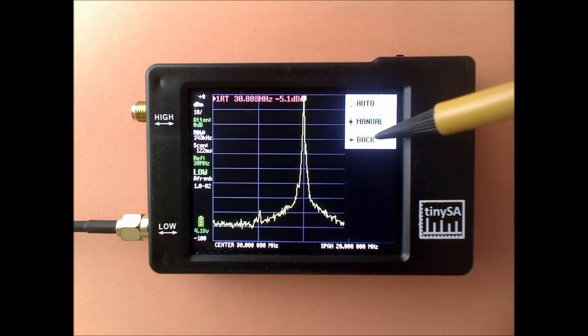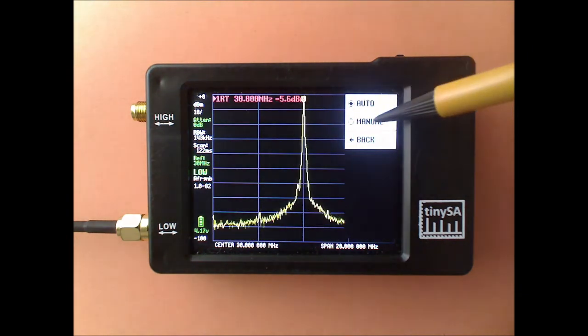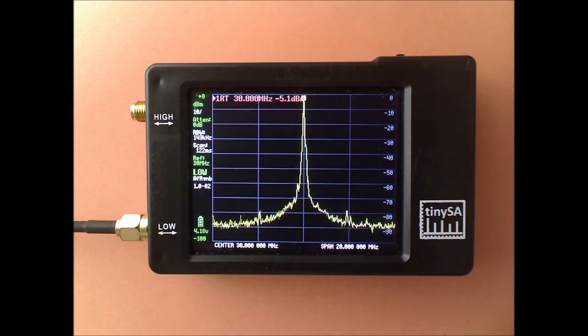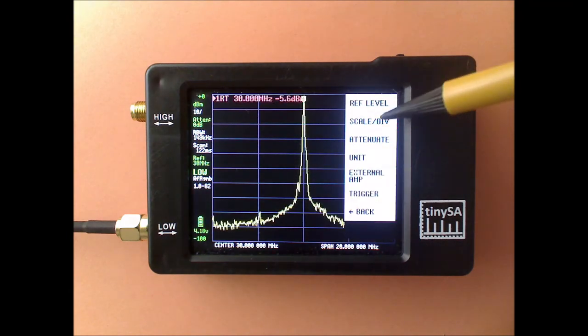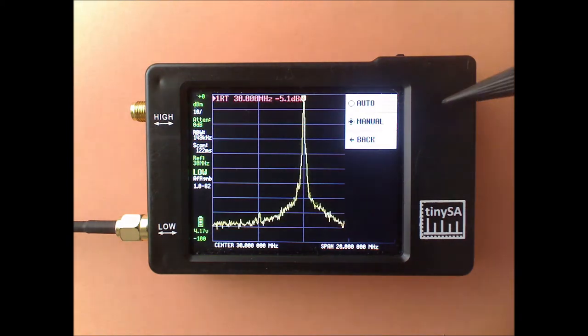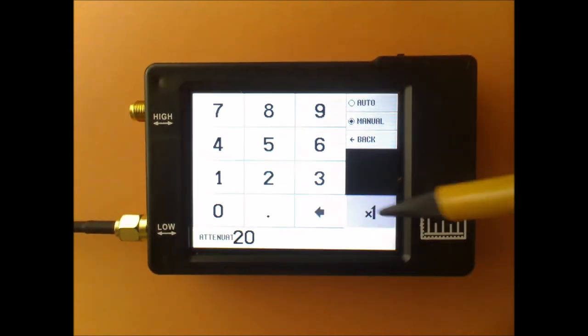Now if I set the ref level to manual 0 dB and I switch between 0 dB attenuation like it is set now and I set it to 20 dB attenuation as it was when it was automatic, you will notice that the noise floor moves up.